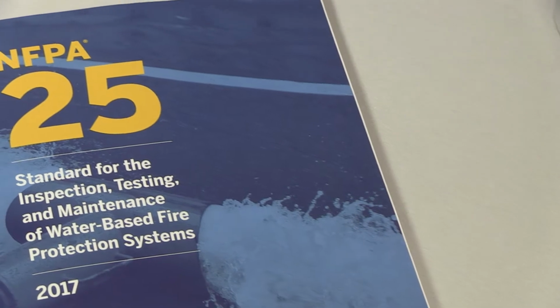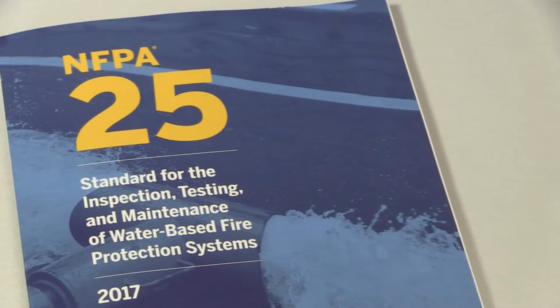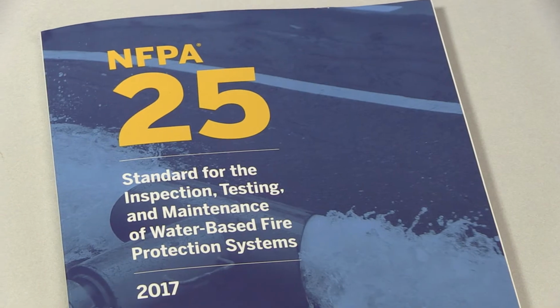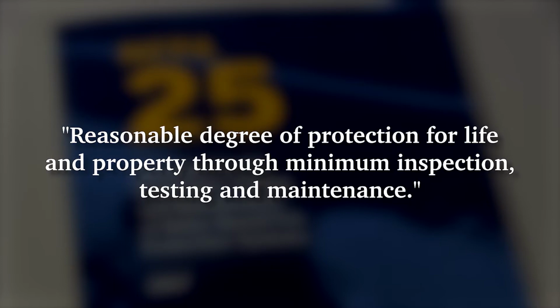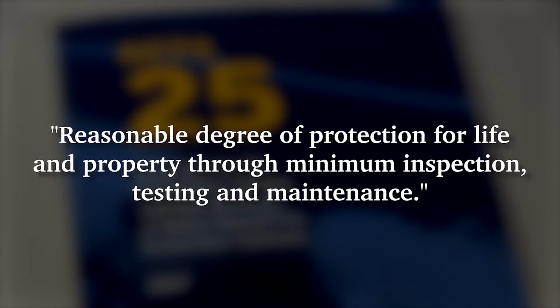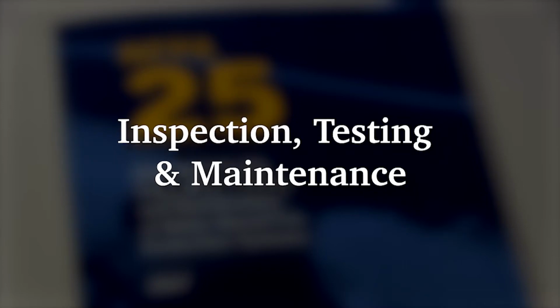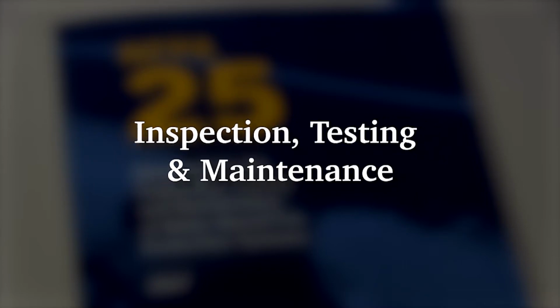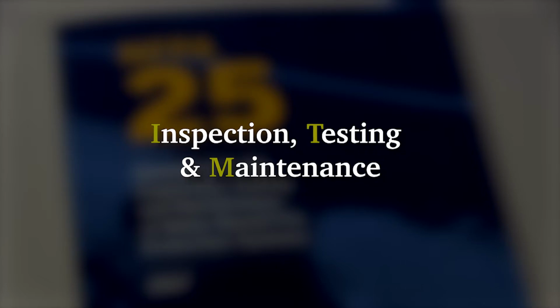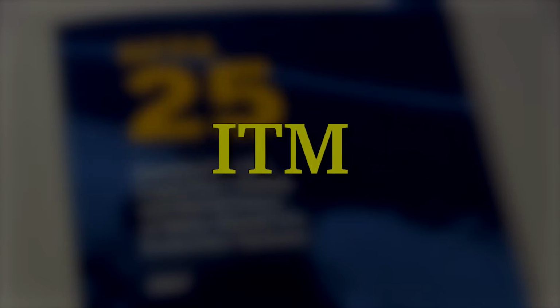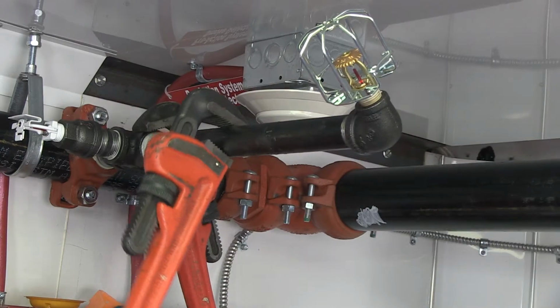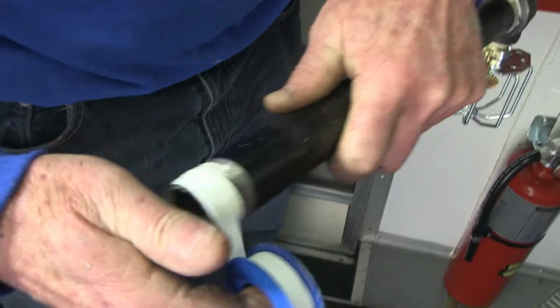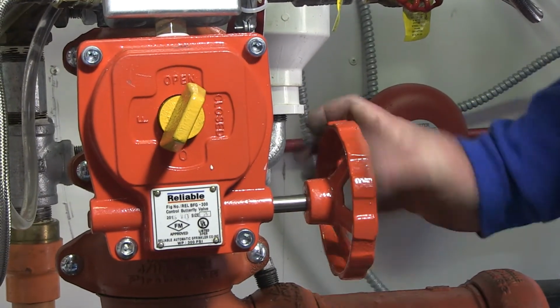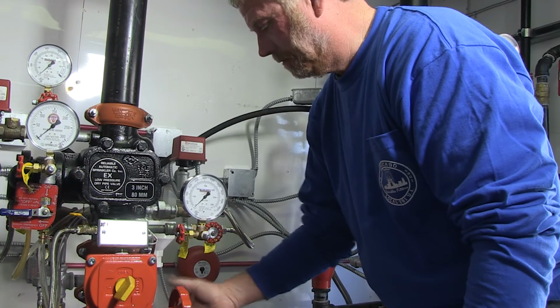NFPA 25 is the standard for the inspection, testing, and maintenance of water-based fire protection systems. Compliance with the standard maintains system integrity and avoids failures, ensuring a reasonable degree of protection for life and property through minimum inspection, testing, and maintenance. NFPA 25 establishes the minimum requirements for the regular inspection, testing, and maintenance, otherwise known as ITM, of water-based fire protection systems. It determines the actions needed when changes in occupancy, use, process, materials, hazard, or water supply that could potentially impact the performance of the systems are planned or identified.